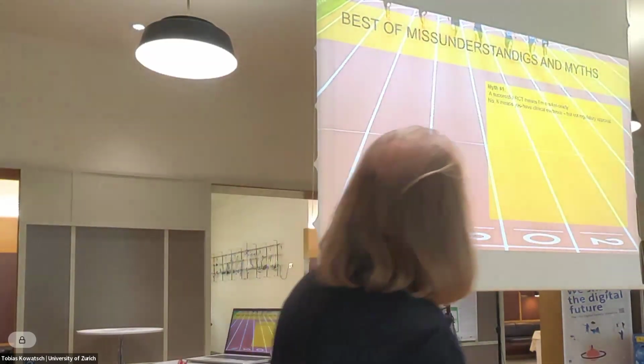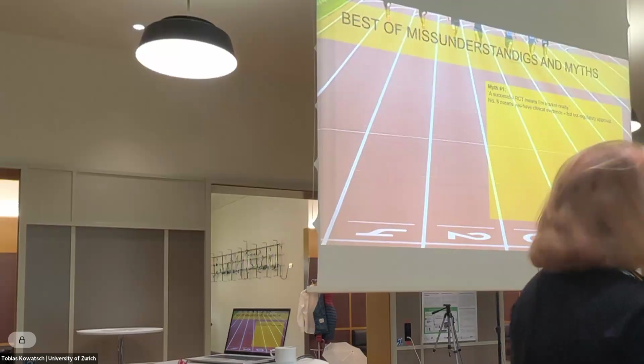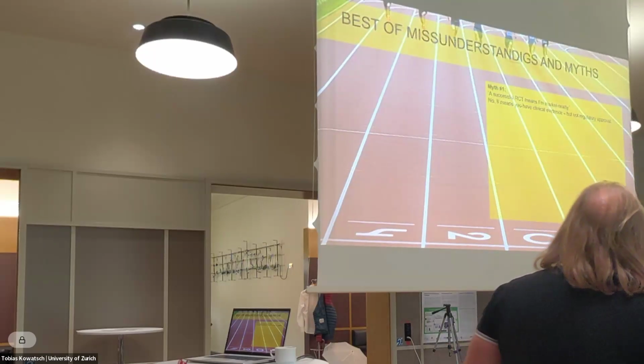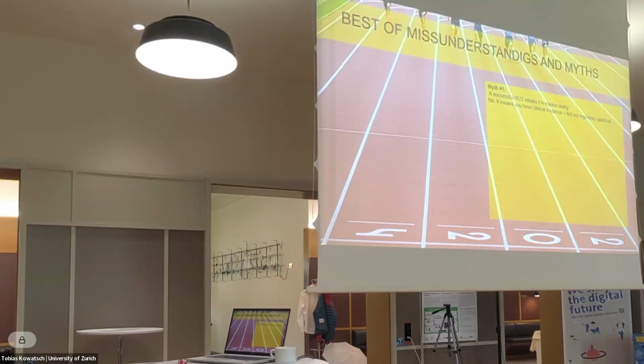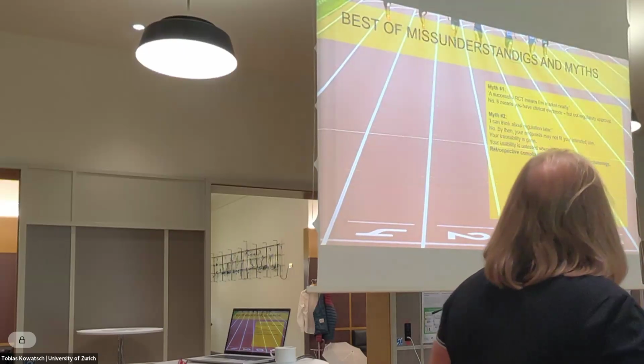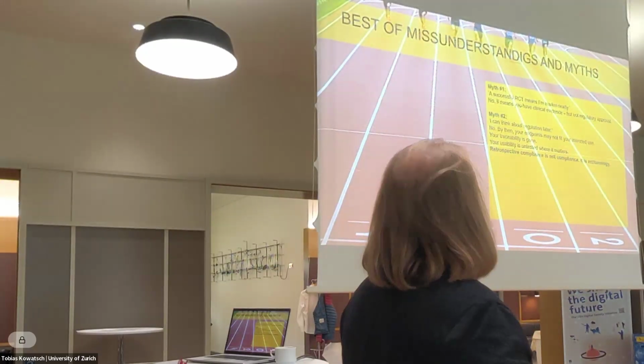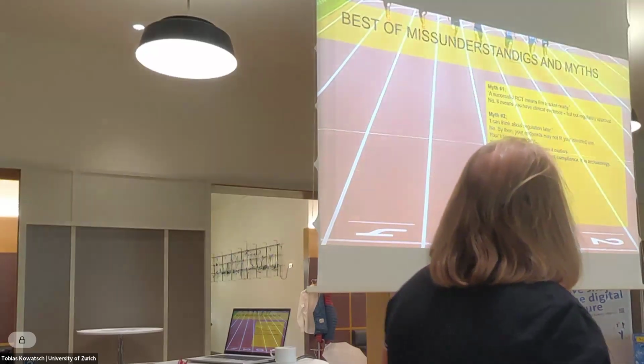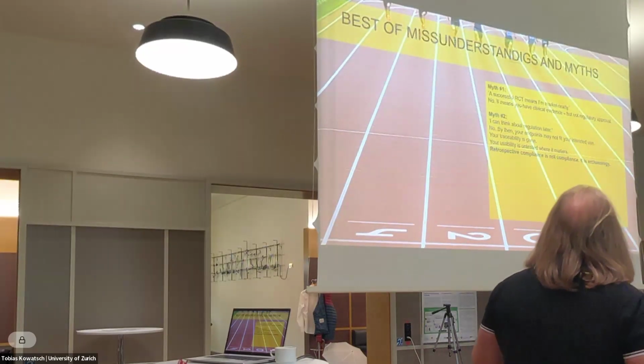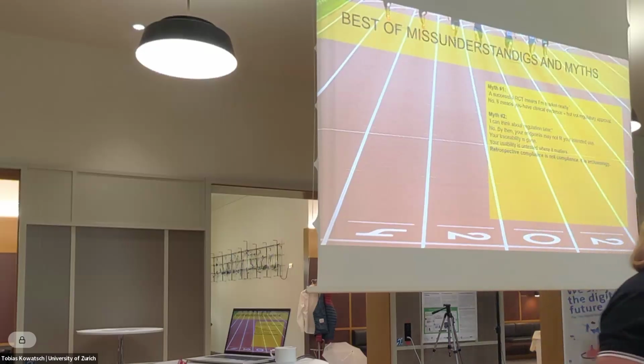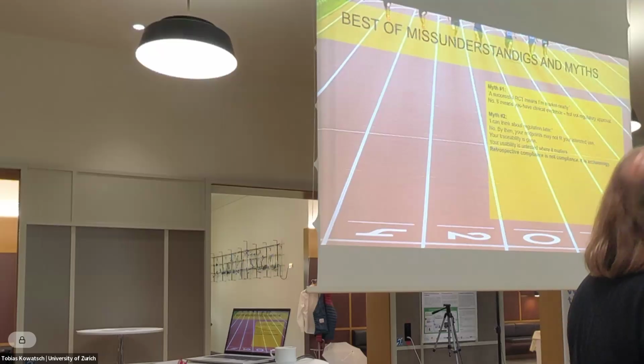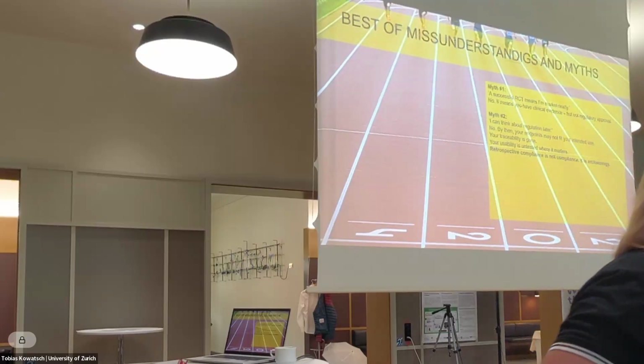Number 1, a successful RCT means I'm market ready. No. It means you have clinical evidence, but not regulatory approval. And if you have not backed your RCT with your technical documentation, then you have what we auditors call only anecdotal evidence. It's worth nothing. The third one, I can think about regulation later. No. By then, your endpoints may not fit your intended use. Your traceability is gone. Your usability is untested where it matters. And retrospective compliance is not compliance, it's archaeology. So that's worth nothing.